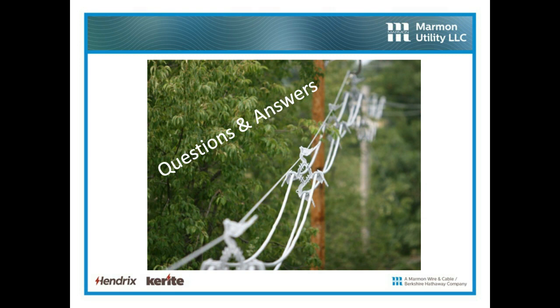Okay, great. Next question: how do you recommend dead ending this conductor? Simple. We recommend dead-ending it in preformed conductor grips that are neoprene coated. They're very long, and obviously there's no tension on these phase conductors, maybe 100, 200, 300 pounds, depending upon what it is. So it's no problem putting them in partial tension preformed dead end grips.